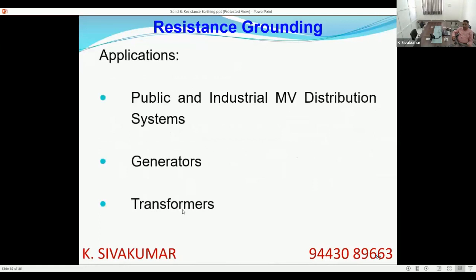Applications: medium voltage distribution, public medium voltage distribution systems, industrial medium voltage distribution systems, where you want to reduce the fault current. Mainly for generator applications, medium voltage generators and transformers. In fact, this is very popular in the United States. So they publish a lot of guidelines and articles on neutral grounding, resistance grounding of neutrals.